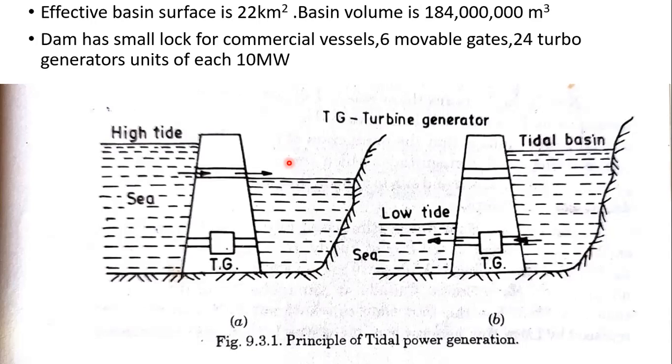Means it can be around 18 crore 40 lakh meter cube. Okay, so there are no special problems with this site, and it is a very sensible choice for the world's first tidal power station. This first tidal power station has used a single basin and submerged reversible propeller type turbine generators. These will generate power with the water flowing in either direction through the turbine runner.